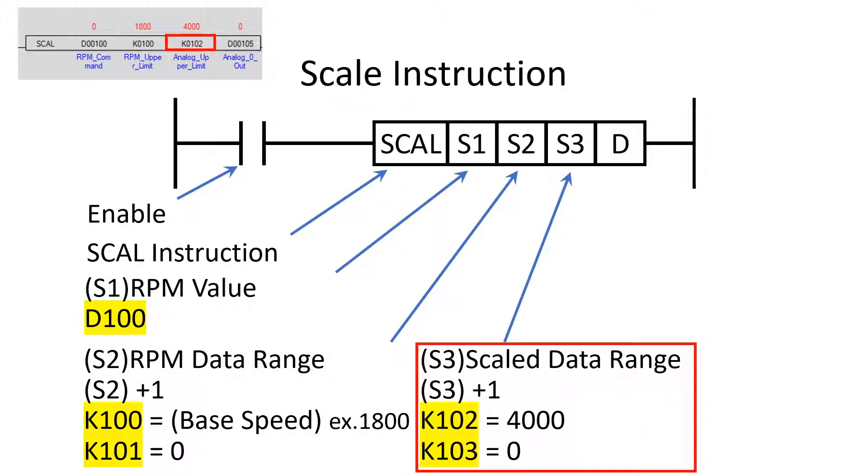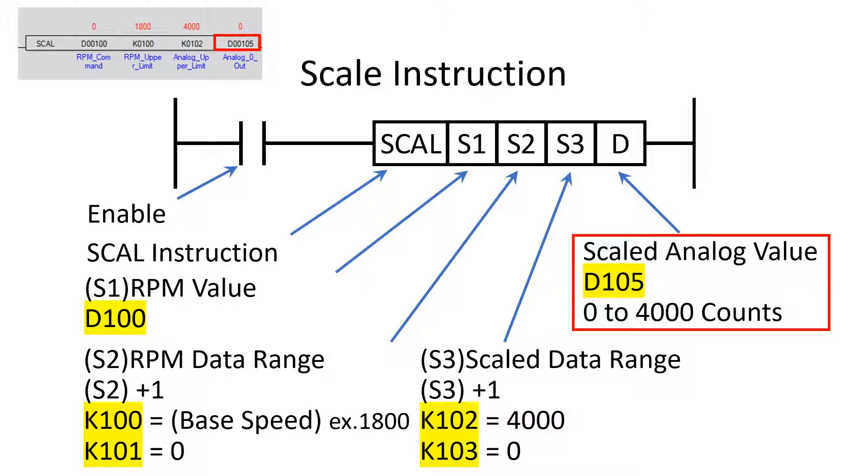The S3 operand stores the scaled range sent to the analog output channel. In this program the scaled range is 0 to 4000 counts which will output 0 to 10 volts from the analog channel. S3 uses two memory locations just as S2. In this program it is K102 and K103 as shown. Operand D stores the scale value for the analog output channel. In this case the analog output count is stored in memory location D105.